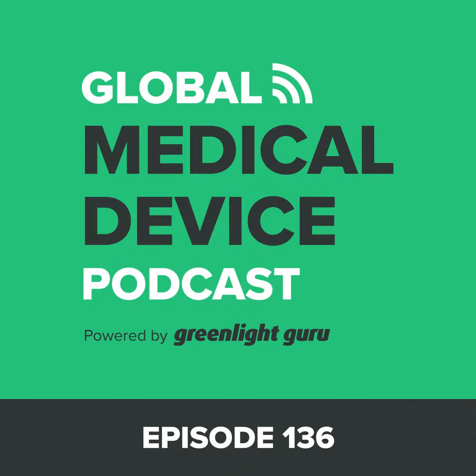But the RTA thing is interesting to me. You said that with the eSTAR program, it eliminates the RTA piece because presumably if you follow the template, then everything that's expected will be included with your 510(k). So I'll ask it open-ended. What are your thoughts about that?